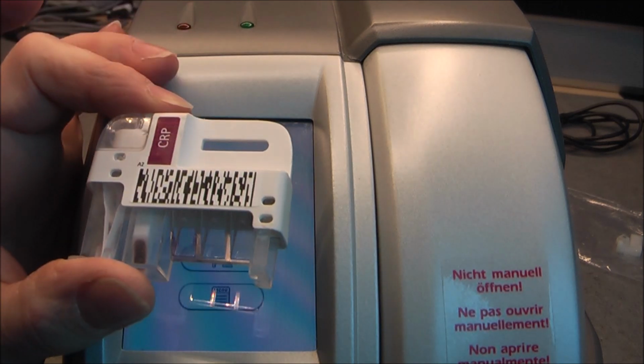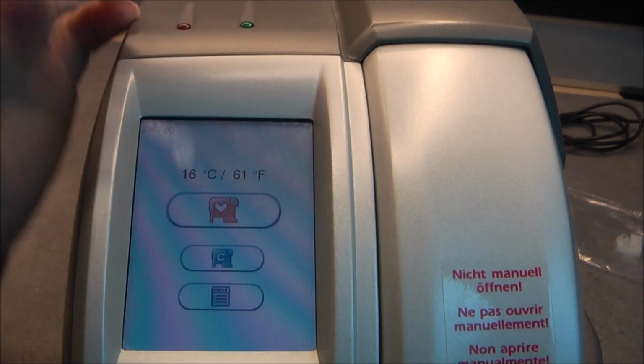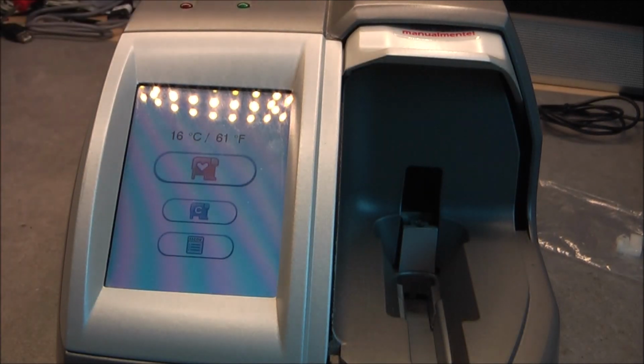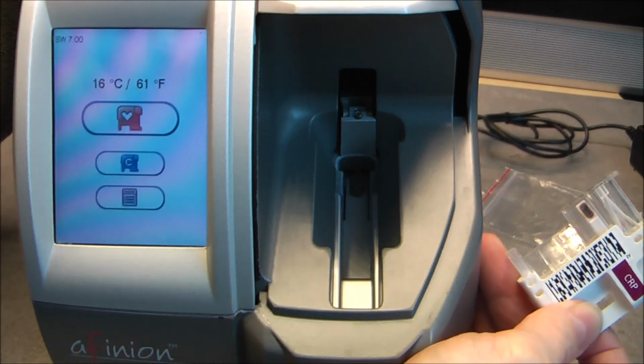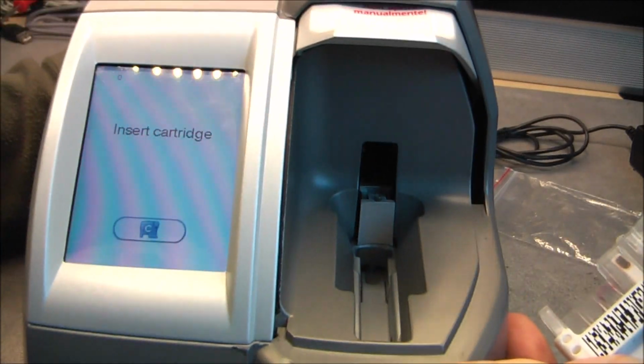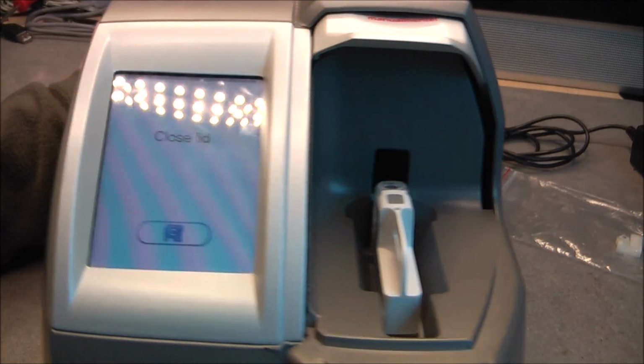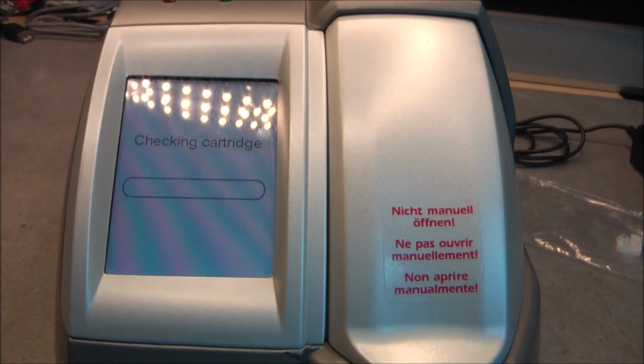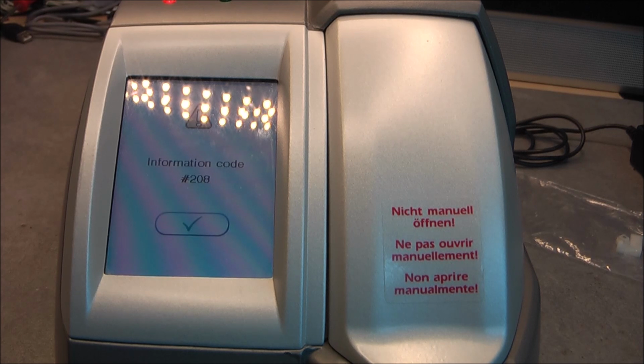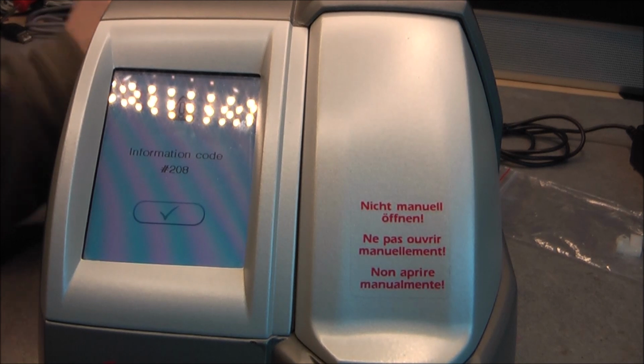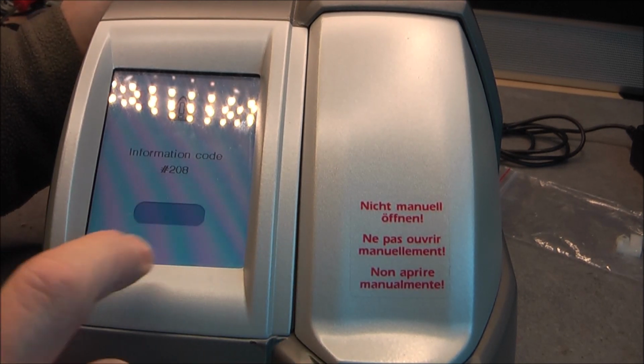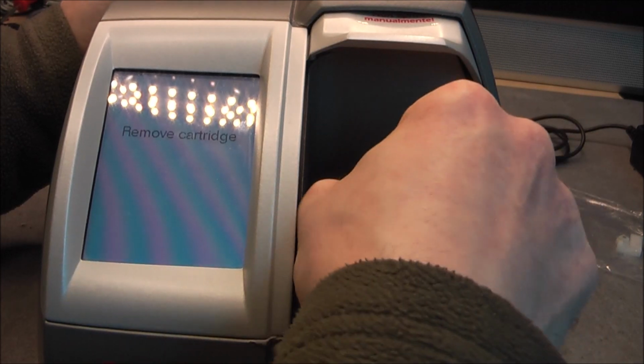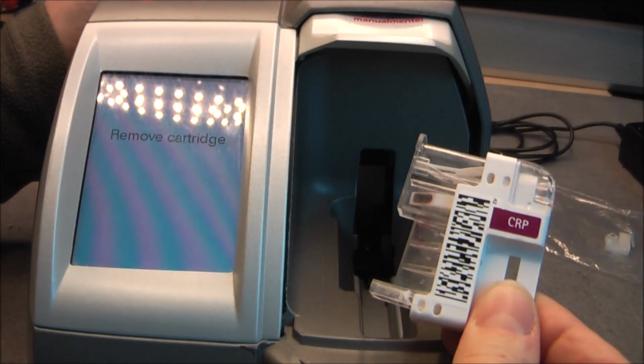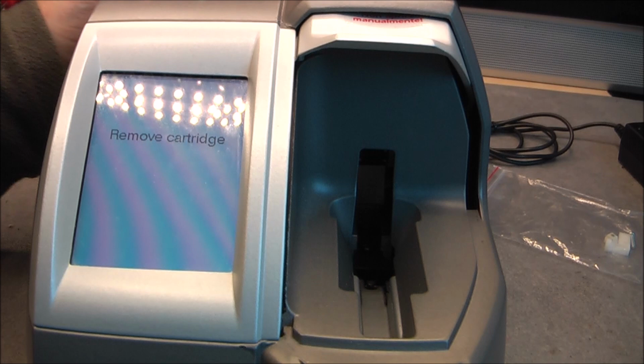I believe with each box of these cartridges you are given a calibration cartridge or something like this. If I press here, it will actually open the receptacle for the cartridge. So I will try to load it and we will see what happens. Close lid. And now it is taking the cartridge and already an error. Okay. Either because it knows it is an expired cartridge, or because it knows there is something wrong inside. Okay, it was not too bad this time, I was able to extract it.